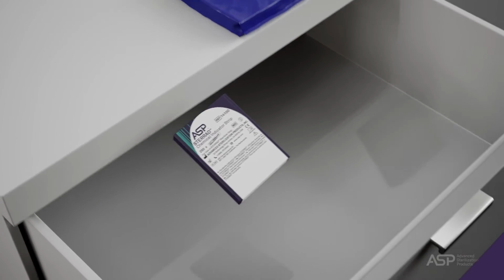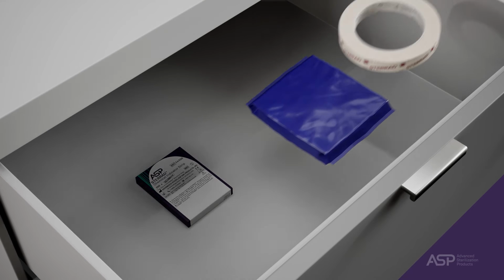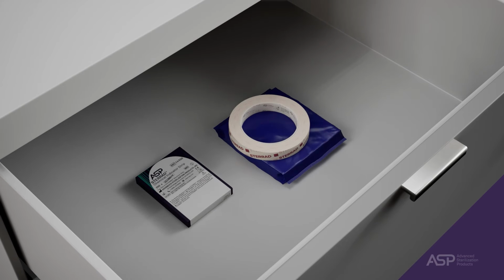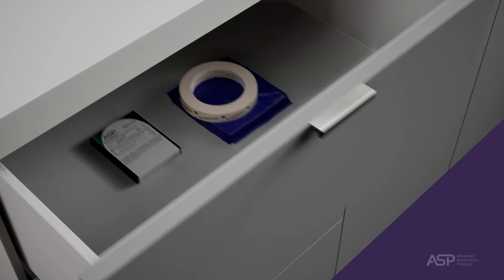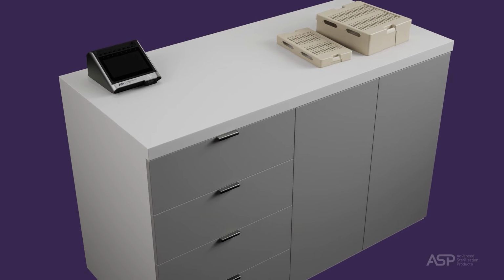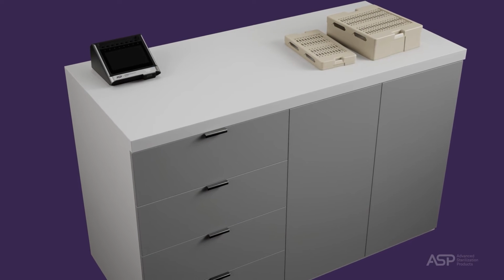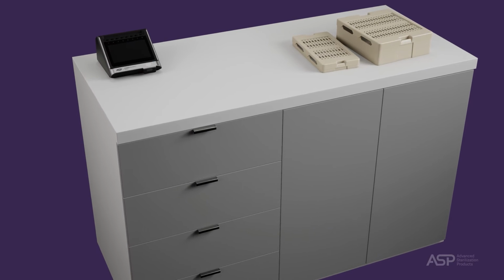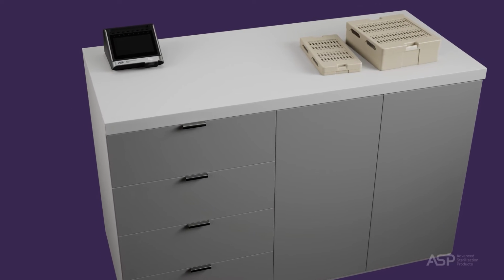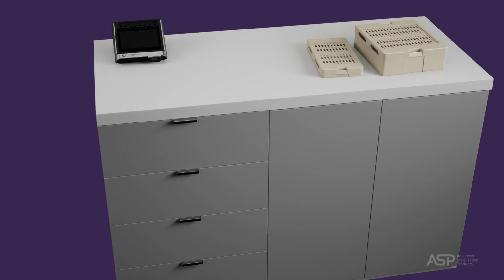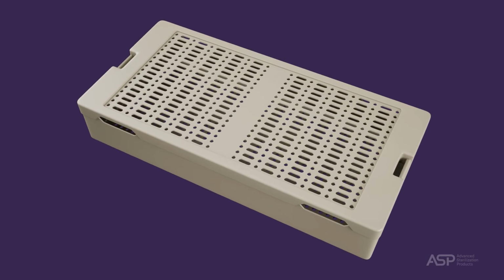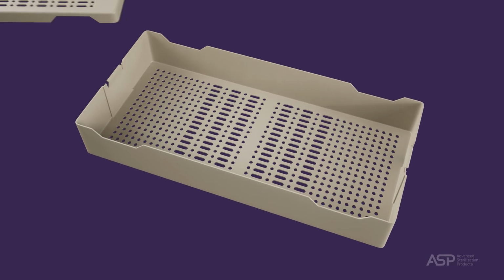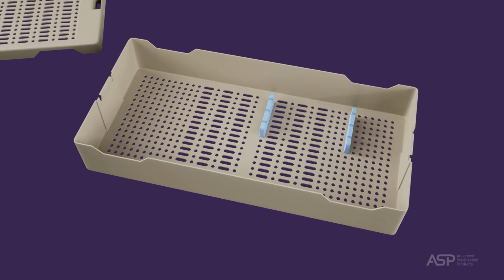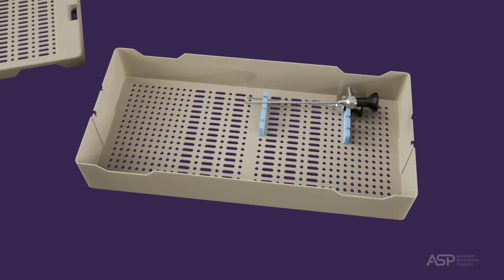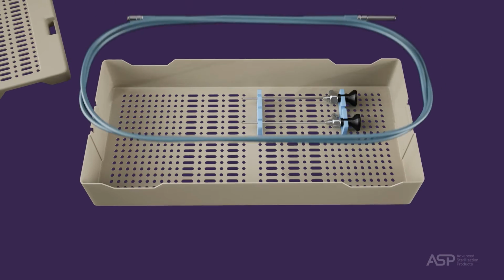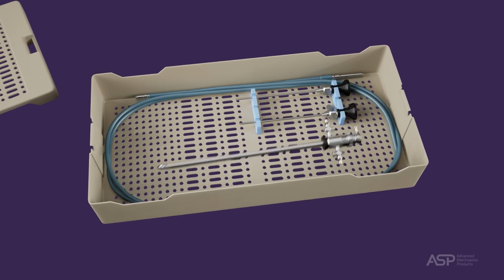Be sure to store the STERRAD chemical indicator (CI) strips indicator box and SealSure chemical indicator (CI) tape away from heat and light. Store chemical indicator strips at ambient temperature, 15 degrees Celsius to 30 degrees Celsius, 59 degrees Fahrenheit to 86 degrees Fahrenheit, under dry conditions. Detailed information on loading and packaging can be found in your user's guide, but the following are some basic guidelines. Arrange items within a tray to ensure proper diffusion of H2O2 throughout the load.